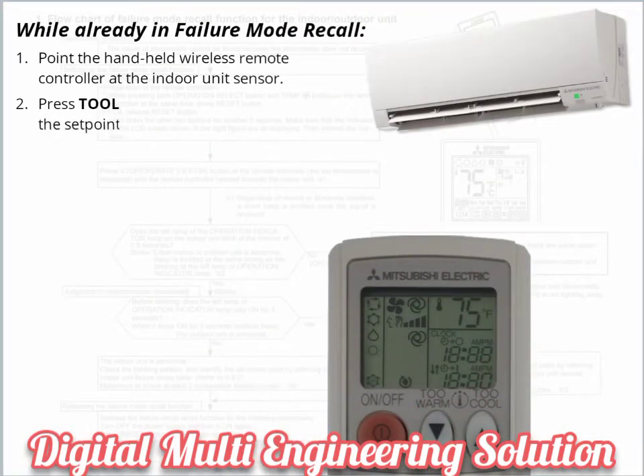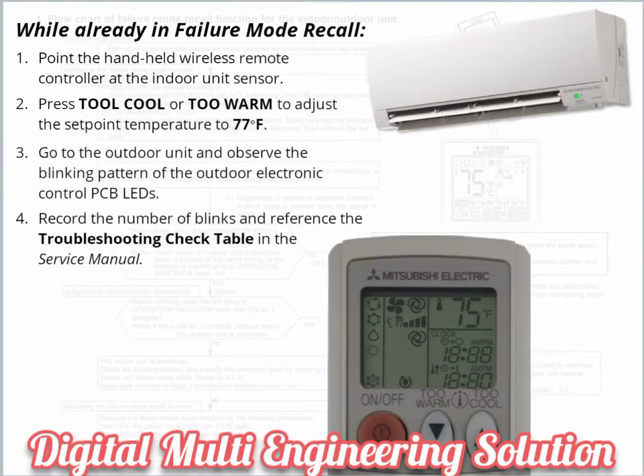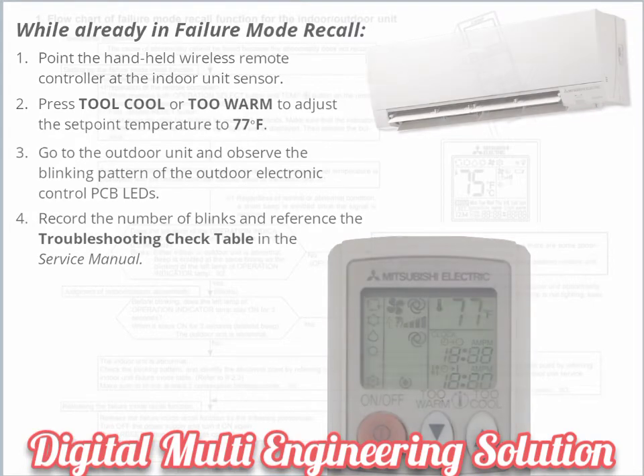If the blinking light pattern indicates an outdoor unit error, point the handheld wireless remote at the unit sensor. Using the buttons, adjust the set point to 77 degrees. Next, go to the outdoor unit and observe the blinking light pattern. Record the number of blinks and reference the troubleshooting check table in the service manual.